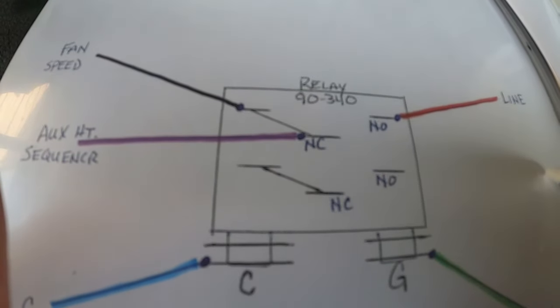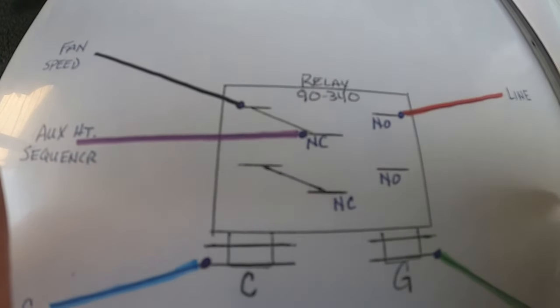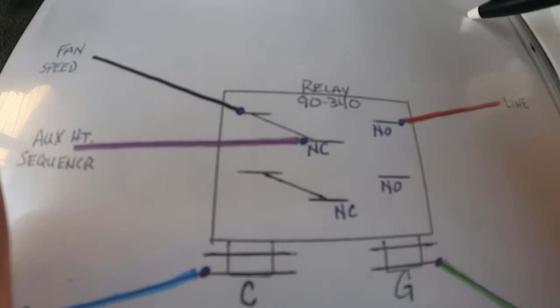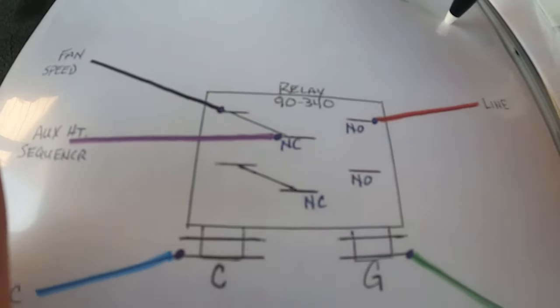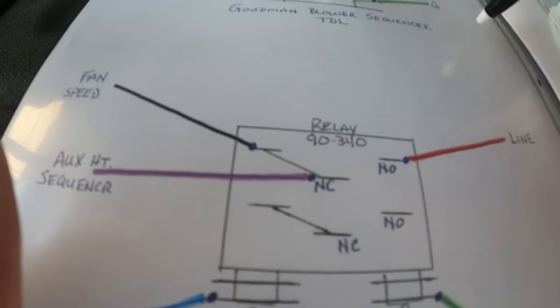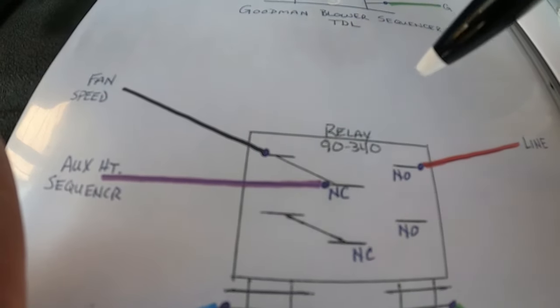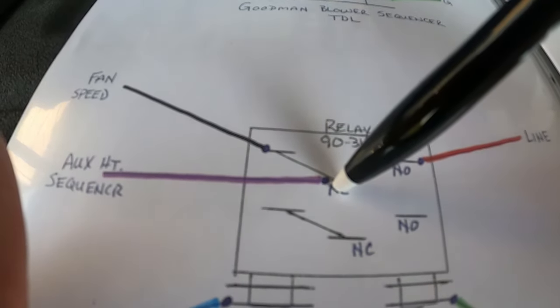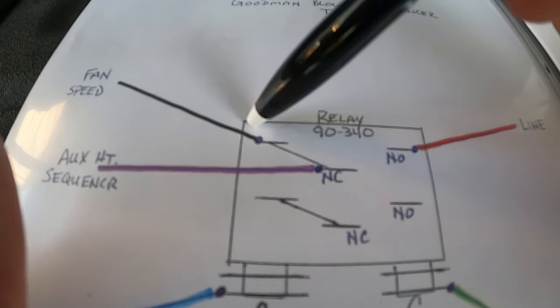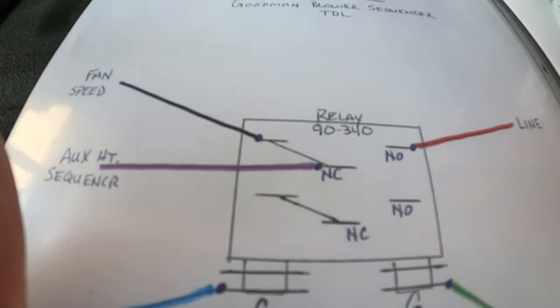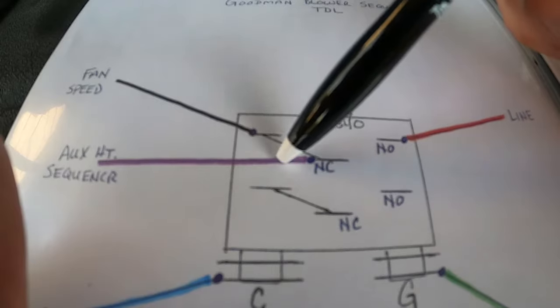If you call for emergency heat or you get a short, something that causes your heat sequencer to energize, when that heat sequencer closes, it's going to backfeed a line voltage to your normally closed switch on this relay, which is in turn going to turn on your blower to ensure that you have airflow.